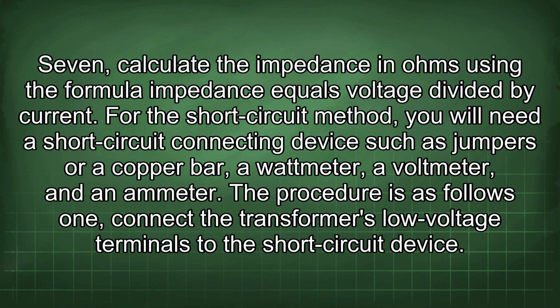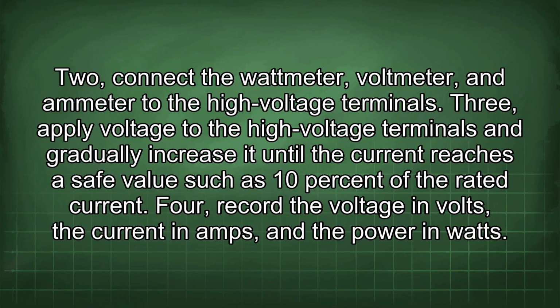For the short-circuit method, you will need a short-circuit connecting device such as jumpers or copper bar, a wattmeter, a voltmeter, and an ammeter. The procedure is as follows. 1. Connect the transformer's low voltage terminals to the short-circuit device. 2. Connect the wattmeter, voltmeter, and ammeter to the high voltage terminals.